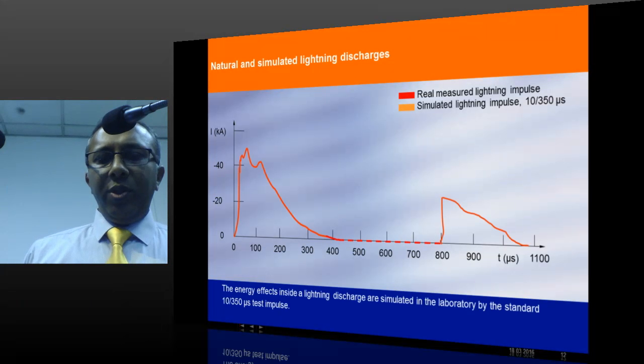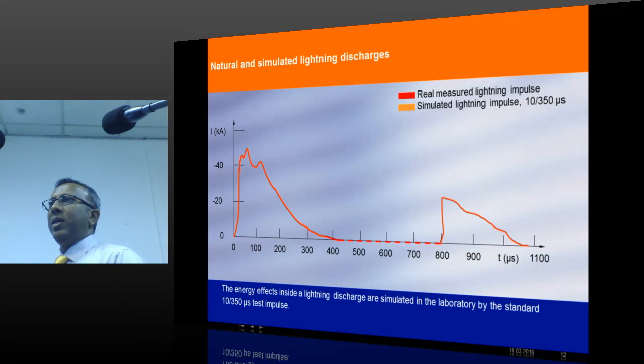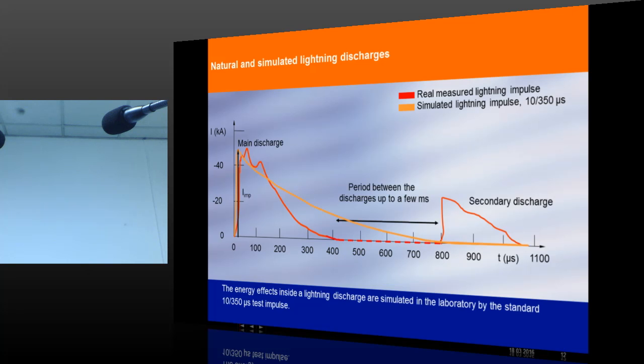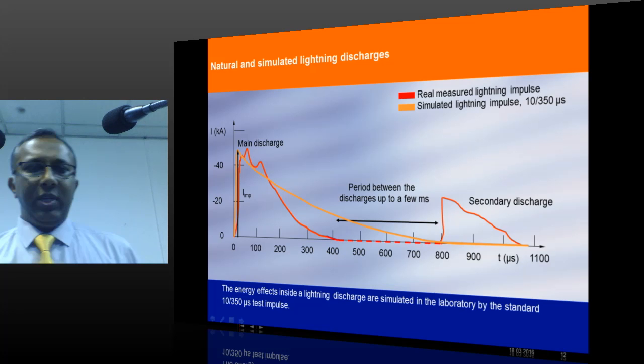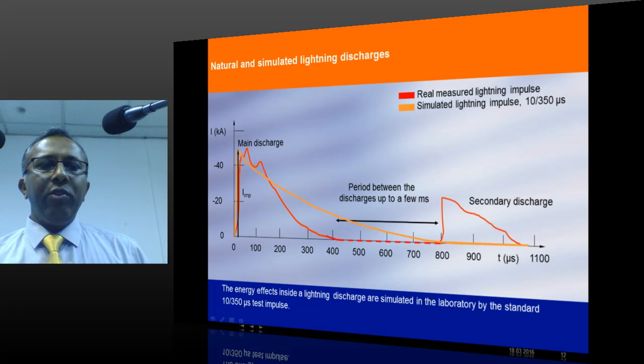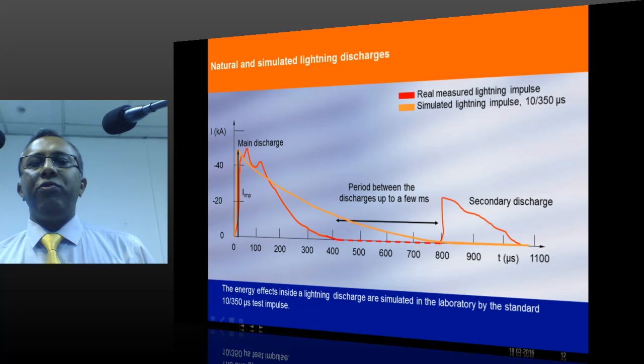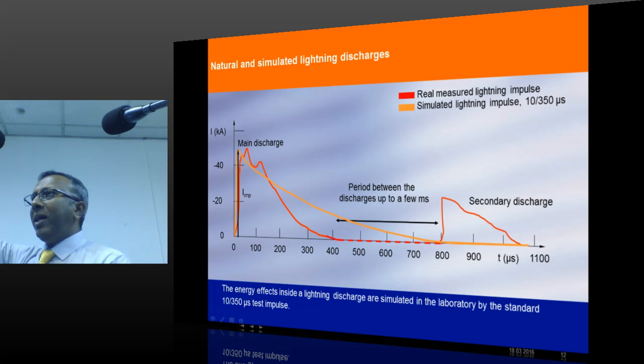So now going to the first slide about the energy of lightning. What is explained in this standard is that lightning consists of a primary strike, the main discharge, and a time. After that, one or several secondary discharges will be there. To protect an installation, what is important is we need to know the amount of energy involved in the main discharge. In the main discharge, you see, current is going from 0 to peak. It is also flowing for some time. The peak current in kiloamperes as well as the time is explained in the standard.